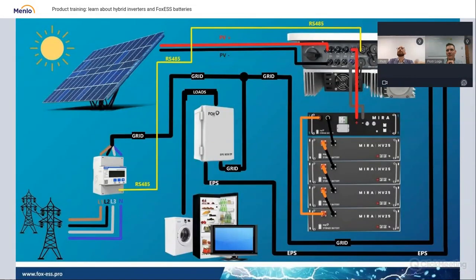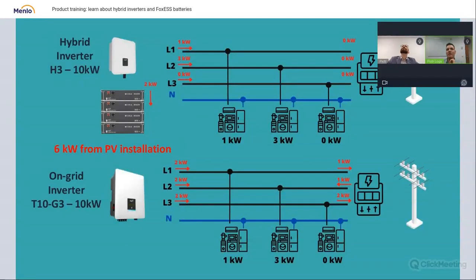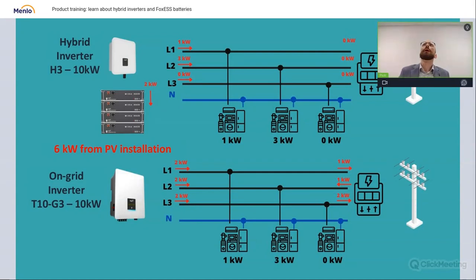Okay, maybe here I can have a question about this slide. Sure. Because as we can see, there are different loads, and let's say two of the phases are taking 0 kilowatts. What's the maximum output that you can give on a single phase? Usually it's a third of the nominal power. So if we have in this example a 10 kilowatt unit, in standard operation, we can output up to 3.6 kilowatts per phase. This is the limit for inverters in general.